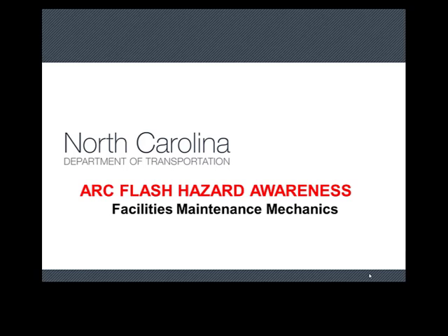In order to perform live electrical work, you must receive additional specialized training to be a qualified person. This means you must be knowledgeable on the types of electrical equipment you will be working with and on safe electrical work practices. This includes skills and techniques to distinguish exposed live parts from other parts of electrical equipment, to determine voltages of exposed live parts, and clearance distances for voltages involved. You must also be trained on what PPE is required to protect you from shock and arc flash hazards. Keep in mind that if you use lockout tagout, you will minimize the potential for an arc flash event.